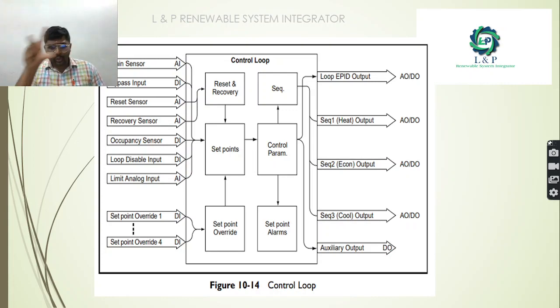So if you're going for a control loop, we have a reset and recovery option, we have a set point option, okay. Most importantly, the set point will come for the occupancy sensors and temperature sensors also. In order to initiate any sort of input, in order to initiate a loop, there needs to be a set point. It can be digital set points also, or in certain places if you want to limit some values, it can be analog input signals as well.